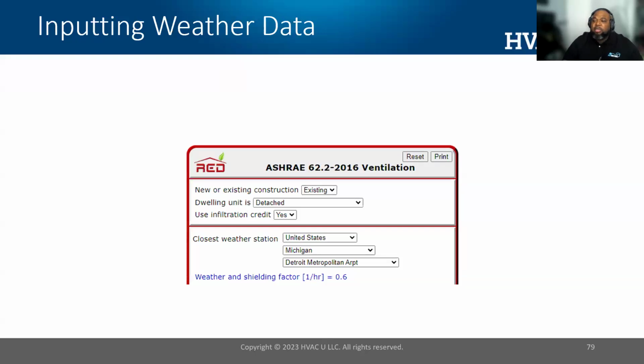All right, an infiltration credit means you're going to rely on the leakiness of the shell to assist in ventilation. Again, that's not a practice I like. The reason why is that building leakage is typically only driven by the difference in temperature between inside and outside. So the building shell leaks the most when the weather is bad. And right now in Michigan, it's relatively cold outside. It's warmer here in my home. The house is going to leak more than it will, say, in the fall, where the temperature is pretty close between inside and outside.